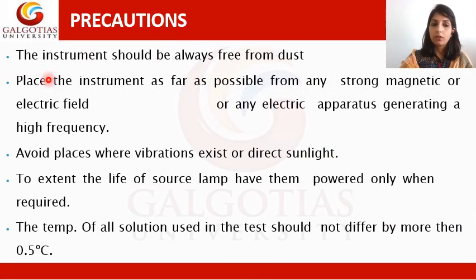Now what are the various precautions? The instrument should always be free from dust. You will need to place the instrument away from possible magnetic and electric fields, as you know that UV visible radiation has electric and magnetic fields and those fields can interact with it. You will avoid places where vibration can exist, because vibrations can lead to excitation. To extend the life of the lamp source, you need to power it only when required. The temperature of the solution should not differ by 0.5%, otherwise the absorbance value that you calculate will not be correct.